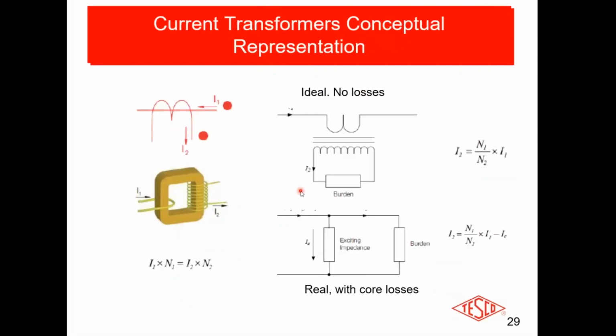Okay. Current transformers: are they ever fast or are they ever slow? Meters could be fast. Typically, they're a little bit on the slow side. The reason for that is meter manufacturers, with one exception, one time, always calibrate up to 100%, which means that typically when you get the meter, it's 99.9 something. It's very close to 100%, but it is not typically over 100%. I'm not saying it can never be, but if you take 10,000 brand new meters, the overwhelming majority of them are going to be just a hair under 100%.